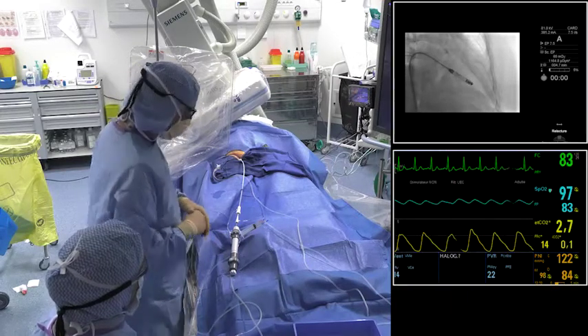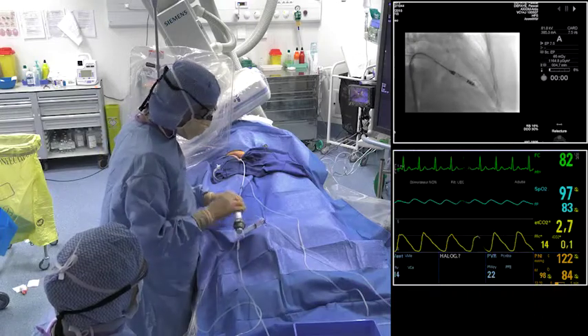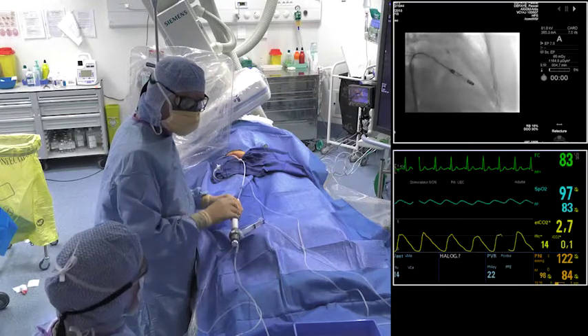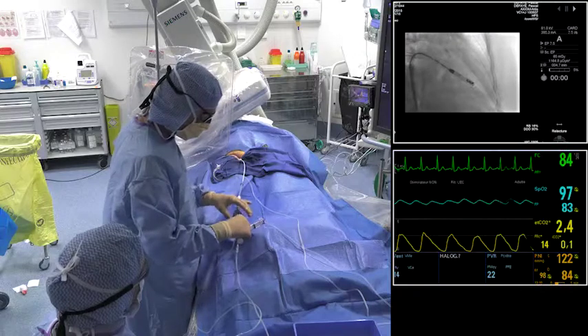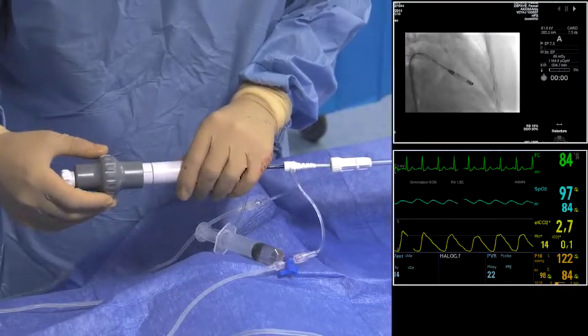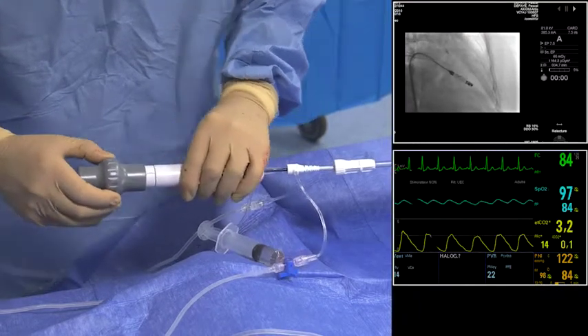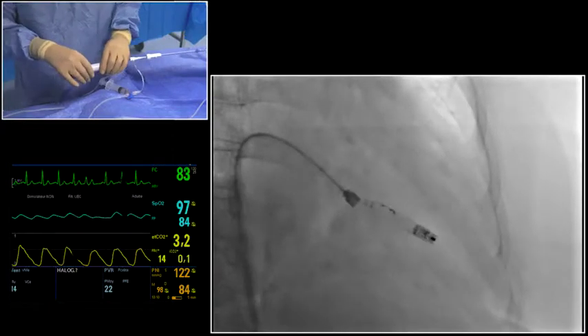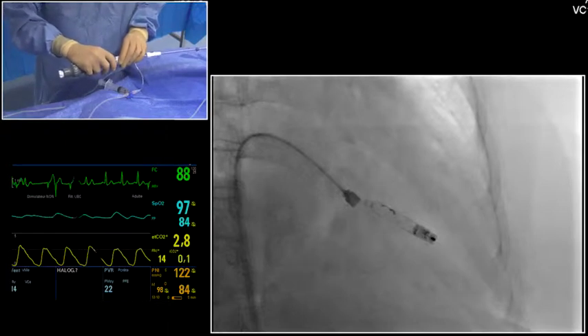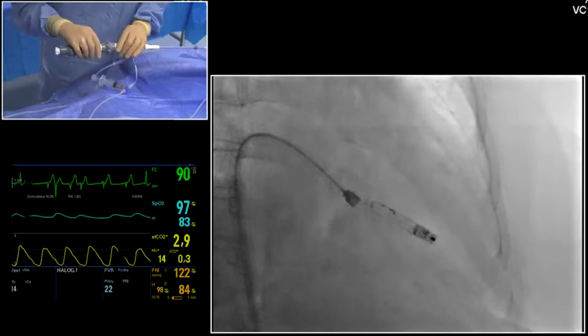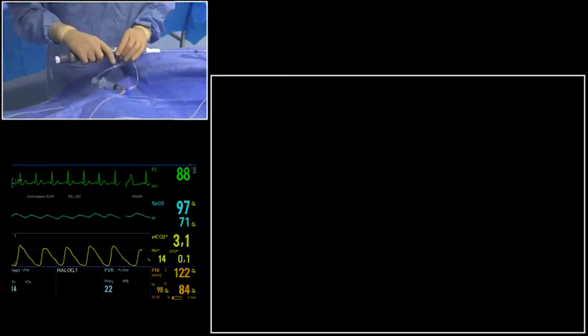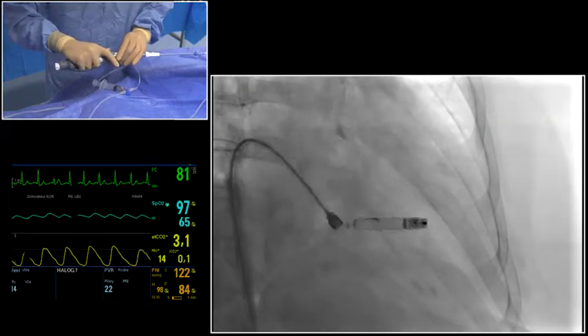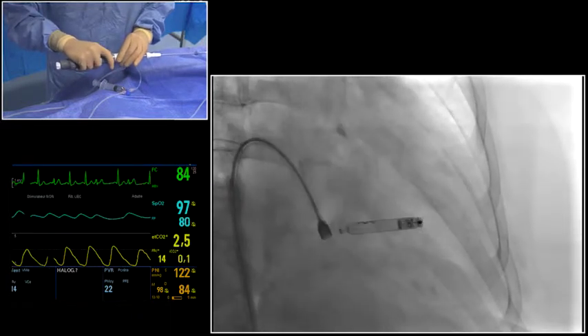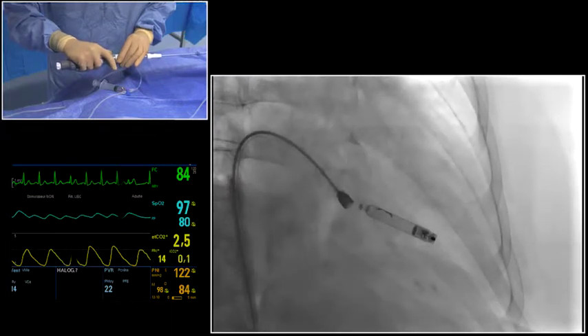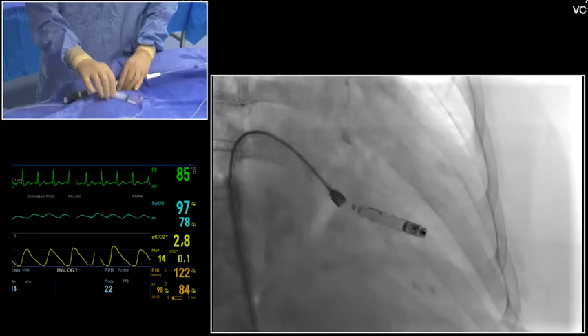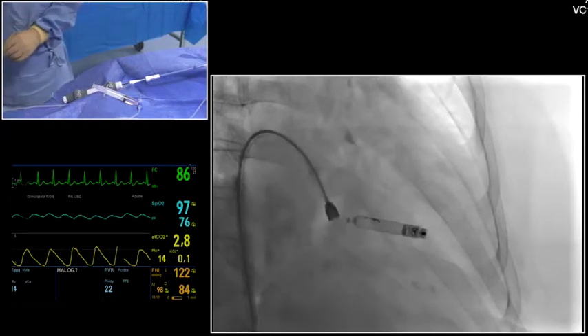We do an image. And then we will do the threshold in passive mode, in tether mode. To be in tether mode, we will undock the handle with these two buttons. Okay. So now we are in tether mode, and we will do a deflection test with my handle and with fluoroscopy, and better in cine. You can see, okay. It's important to do a 30-degree deflection to be sure that the nanostim is well screwed inside the right ventricle.